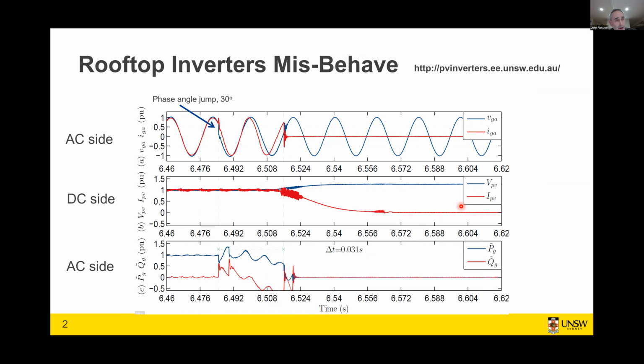So we probably all know by now that rooftop inverters misbehave. Here's an example of a 5 kVA inverter tripping off in 1.5 cycles with a relatively benign phase angle jump of 30 degrees. This was work we did at UNSW as part of a bigger project with AEMO, where we set out primarily to develop a model that the transmission network operators could use, one that modeled to some extent the distributed PV that they would be transmitting their bulk energy towards.